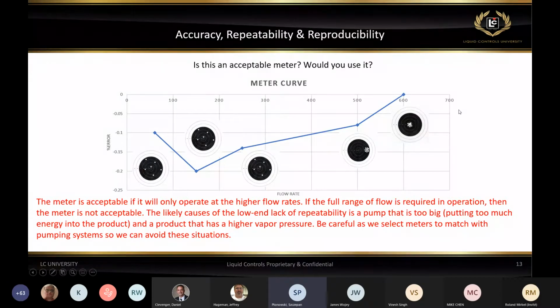Because again, when you're calibrating a meter, when you're testing a meter, you're not testing only the meter alone. The meter is really an indication of what's going on in the system. And if the system is not operating correctly, the meter will show that. And that curve illustrates that example.